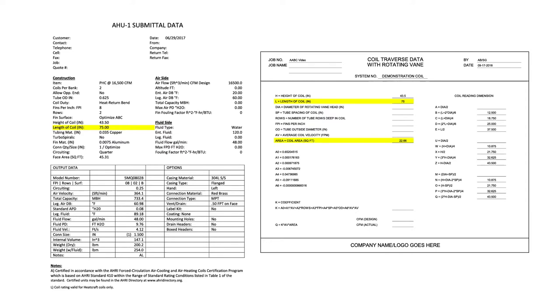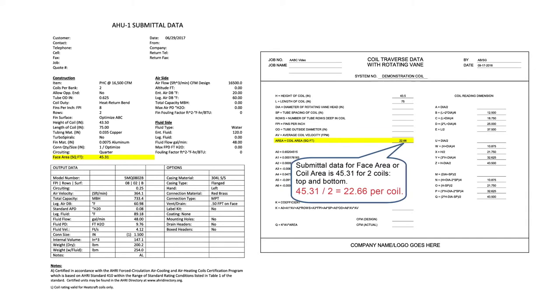Verify the coil area with the submittal data sheet. On the AHU-1 submittal data sheet, face area is documented as 45.31 square feet for two coils, top and bottom. Therefore, each coil's face area or coil area is 45.31 divided by two, which is 22.66 square feet for the top coil and 22.66 square feet for the bottom coil.